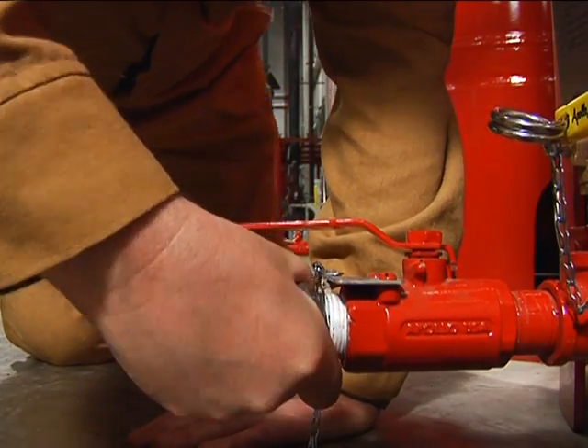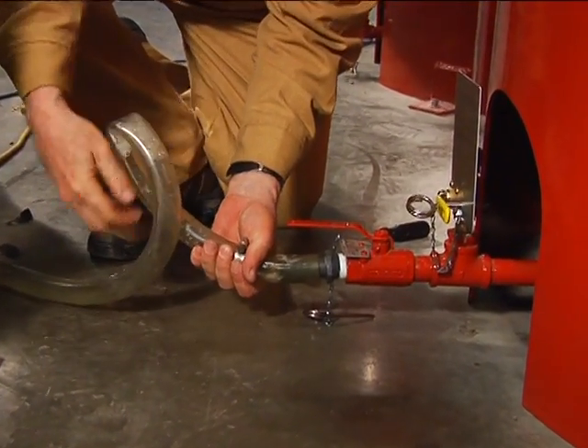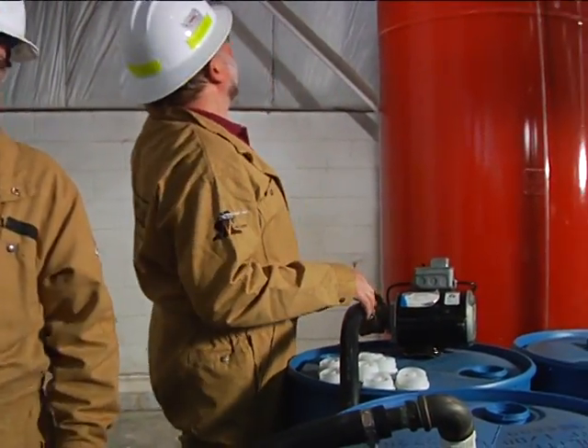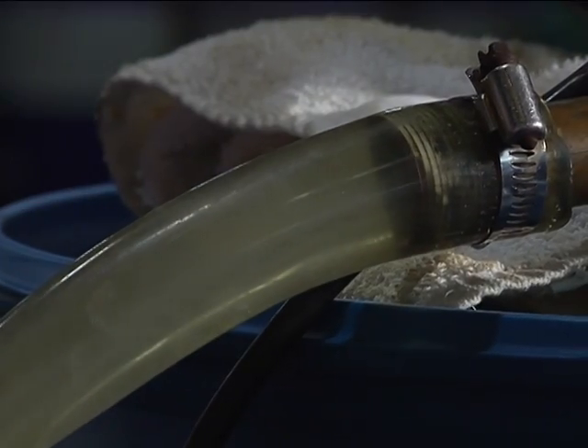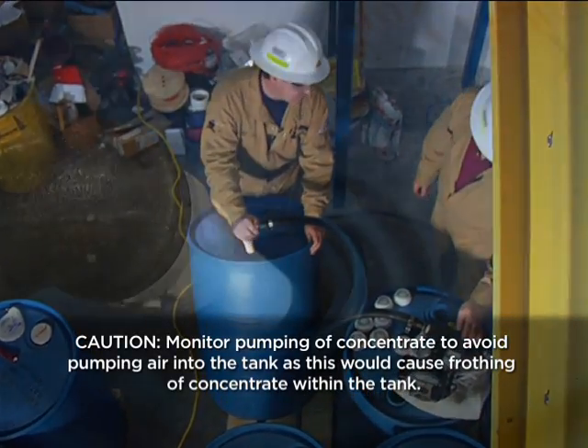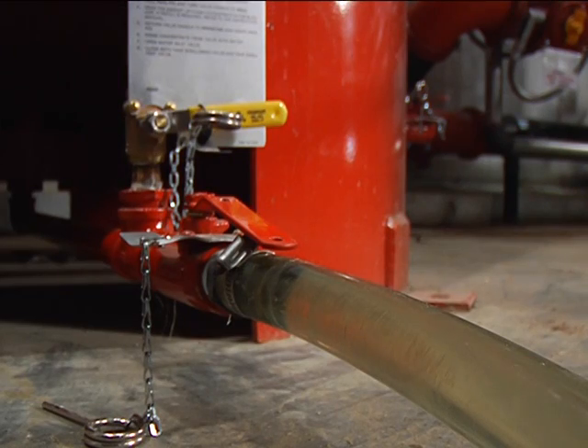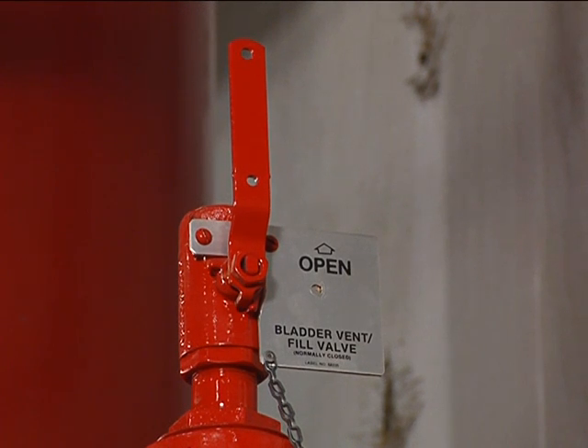Connect the pump to the bladder drain fill valve. Keep in mind that only the Ansul foam concentrate specified on the tank nameplate may be pumped into the bladder. Start the concentrate pump and open the pump valve. Proceed to fill the bladder tank with the Ansul concentrate. At this point, the only valves that should be open are the pump valve, the bladder drain fill valve, and the bladder vent fill valve, which is venting the air being displaced by foam concentrate.